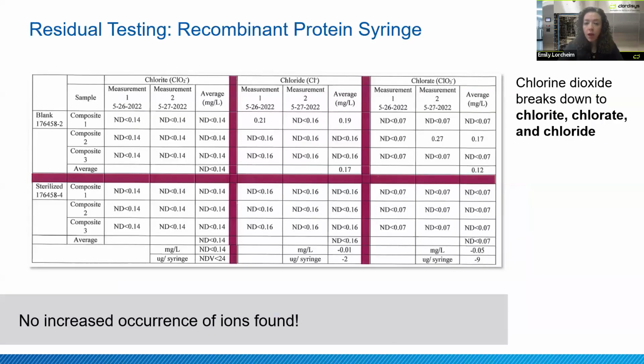Now, I did mention that with chlorine dioxide gas, it will break down into chlorites, chlorates, and then into chloride. Most of the time, you don't even see these ions detected after sterilization, and you'll even see levels, especially of chloride, before sterilization. So what we do is we take a control sample and a sterilized sample and test them through ion chromatography testing. But again, in most instances, you don't even see an increased occurrence of ions found. So you would do this mostly on your device. However, a lot of people do it on their packaging as well.